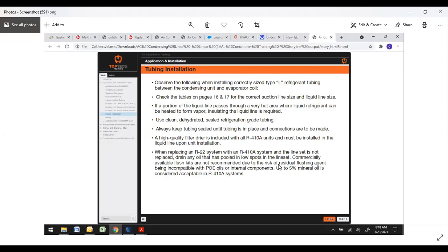Commercial flush kits are not recommended due to the risk of residual flushing agent being incompatible with POE oils or internal components. Up to 5% mineral oil is considered acceptable. You definitely want to use a fair amount of high pressure nitrogen to flush anything that's out of those lines. Some guys still use flush kits, providing they use enough nitrogen with them and don't get chintzy on the nitrogen. They can usually flush all that out, but you do want to make sure you start with as clean of a system as you can possibly start with. If you don't, a lot of times the problems won't show up immediately. It will start showing up 4, 5, 6 years later with compressor failures and other issues.